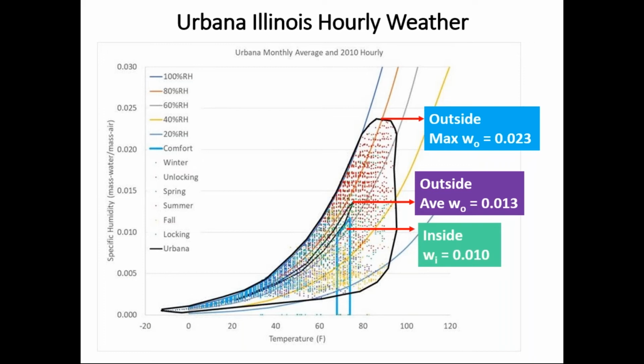Now, as far as moisture transport into a home by infiltration or ventilation, the difference in the humidity ratio between inside and outside dictates how much water is going into a home or out of a home. So if we were trying to keep the inside of a home at 0.01 humidity ratio, basically about 72 degrees with 60% relative humidity, and the outside, in the smaller black outline, the top of that is our summer average humidity for central Illinois, about 0.013. But you can see we do hit some extremes that will go as high as 0.023, something similar to what you'd see in Miami and New Orleans.